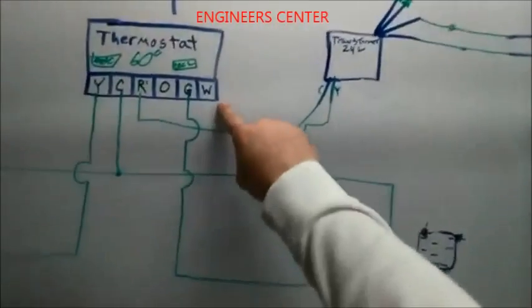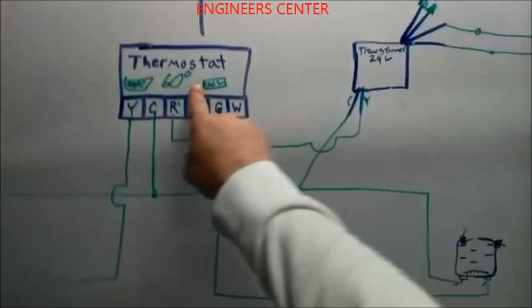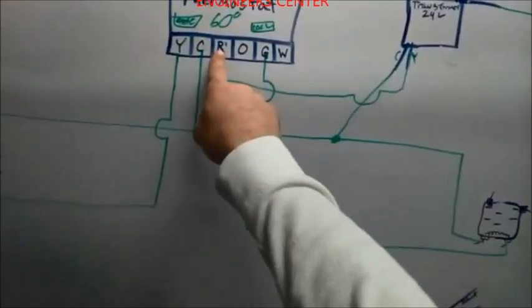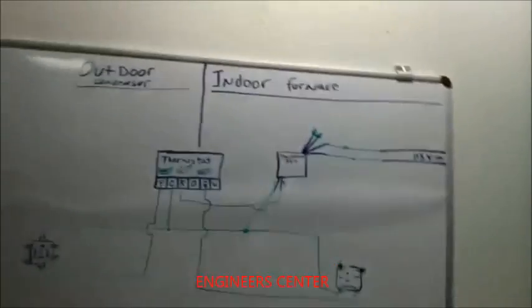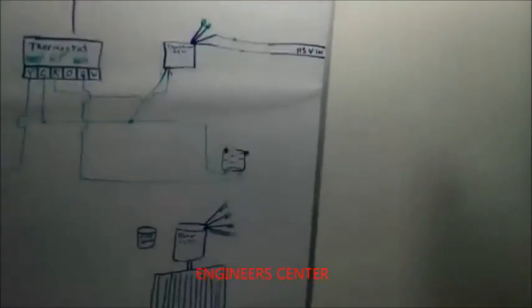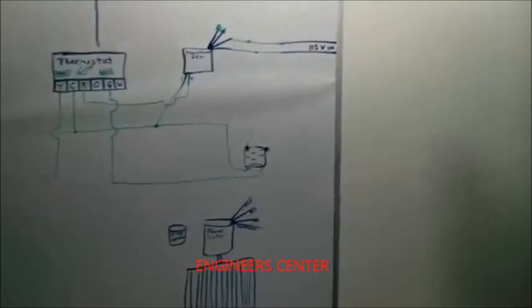If we were going to do heating, which we don't have a lot of room on this diagram, we would simply put this thing into heat, and now it would send the red wire to white, and it would go now and control your heating relays that would work the exact same way. Different relays, opening and closing. So now that our low volt is done, let's do our high volt.